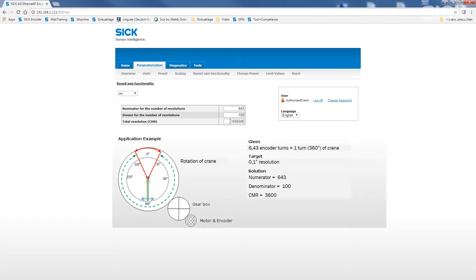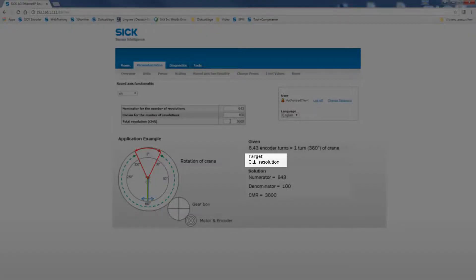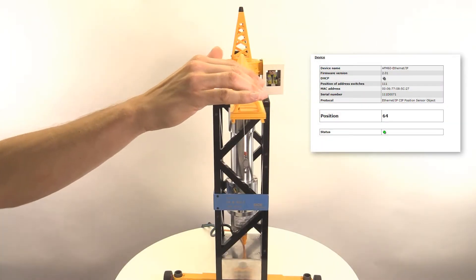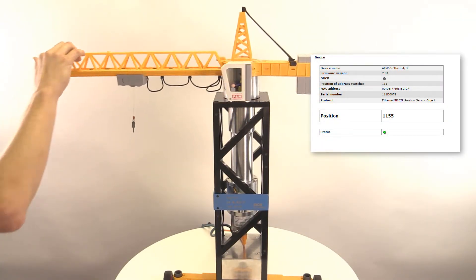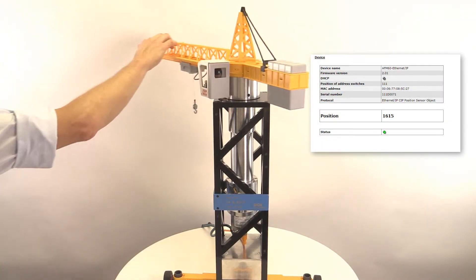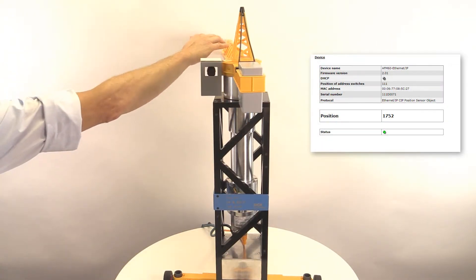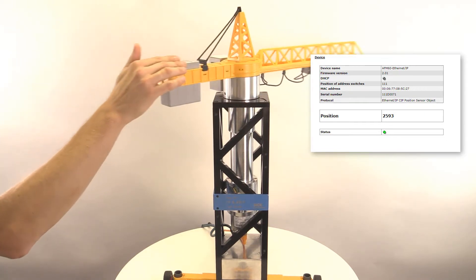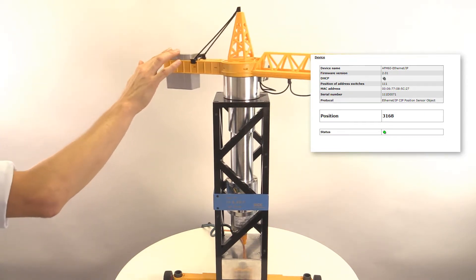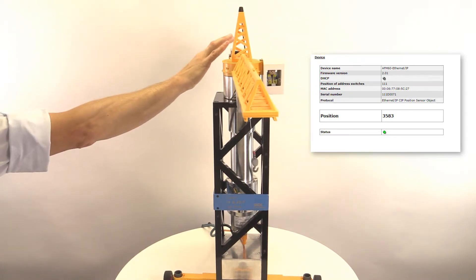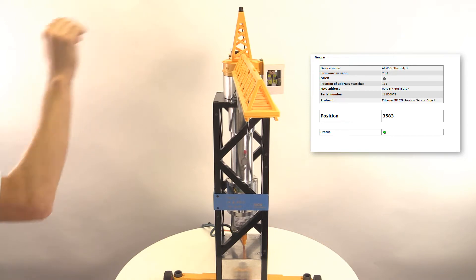In addition, we have to set the total resolution to 3600 position steps in order to have a resolution that equals 0.1 degrees, referring to one turn of the application. Now, one turn of the boom equals 3600 position steps of the encoder. With this, the encoder is exactly adapted to the application.